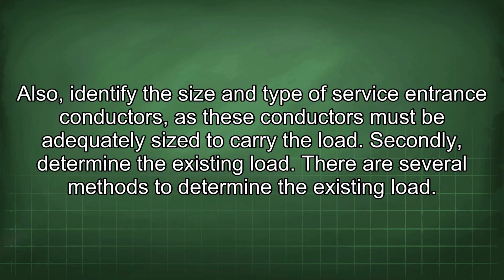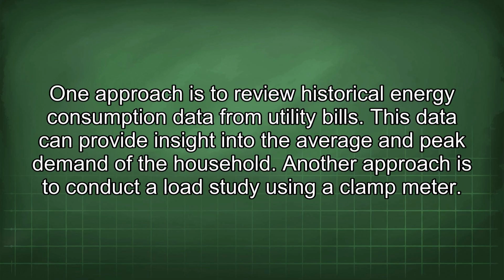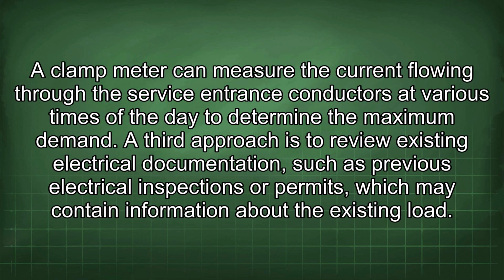There are several methods to determine the existing load. One approach is to review historical energy consumption data from utility bills. This data can provide insight into the average and peak demand of the household. Another approach is to conduct a load study using a clamp meter. A clamp meter can measure the current flowing through the service entrance conductors at various times of the day to determine the maximum demand. A third approach is to review existing electrical documentation, such as previous electrical inspections or permits, which may contain information about the existing load.